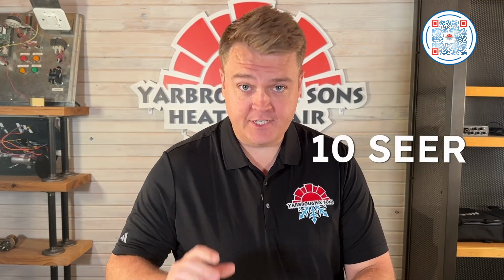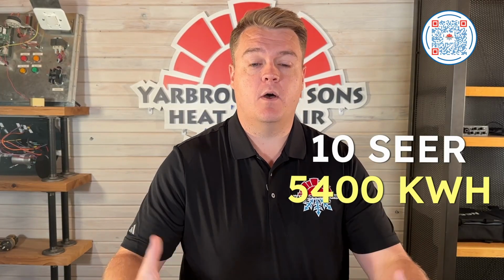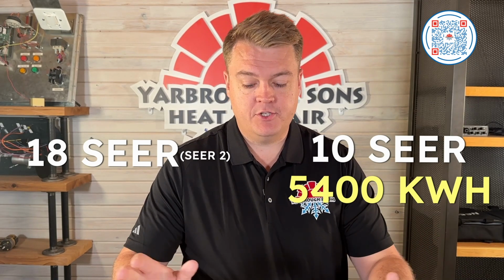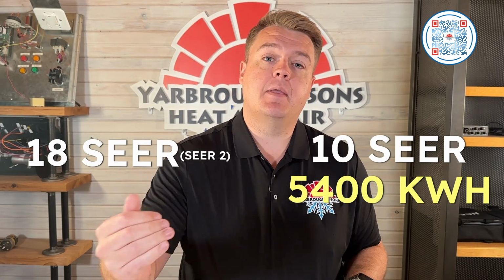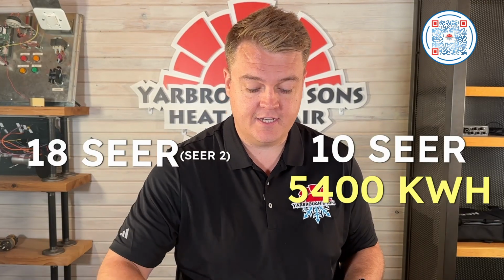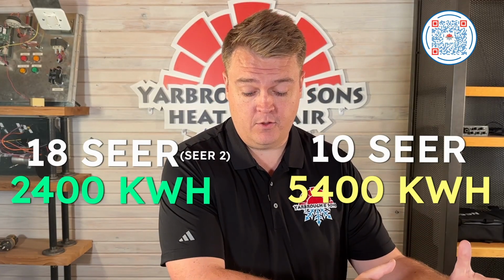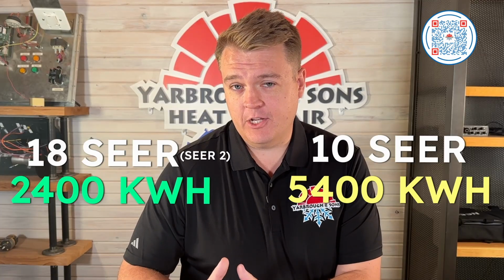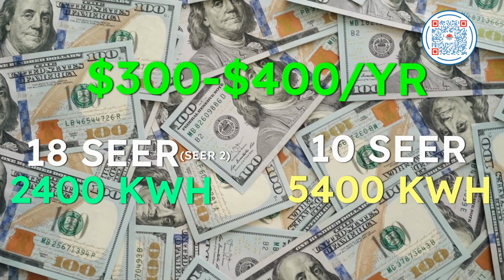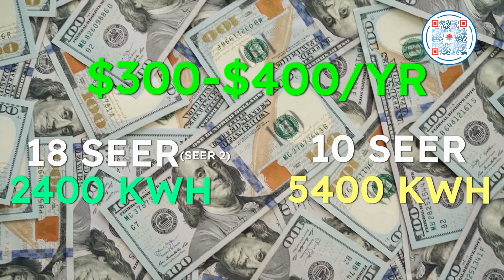And at a 10 SEER system, like what we were talking about in the beginning, we have 5,400 kilowatt hours that get used while this system is running. Now, the 18 SEER 2 system is going to cool for the same number of hours, the 1,500 cooling hours. However, because it draws less, or uses less fuel in our miles per gallon scenario, it's able to do it at just 2,400 kilowatt hours as opposed to 5,400 kilowatt hours. So with a rough average cost of electricity being 12 cents per kilowatt hour, over the course of each year, we're going to see about a $300 to $400 savings in utility bills on this 18 SEER 2 system over repairing our existing system.